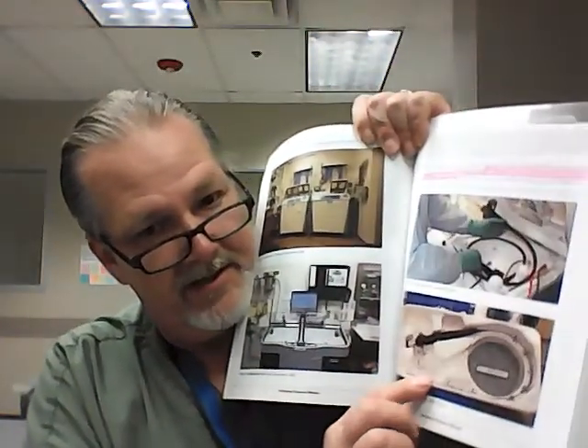This card right here is attached to a little chain, which is attached to a little cap. And the little cap is attached to the scope. This is extremely important: that cap must be attached to the scope before the scope is wrapped up and sterilized. The scope will get sterilized in a sterilizer that will draw vacuum. If you do not have that cap on, then you don't have the passageway open, there may be air inside of there, and that air will expand under the vacuum of the sterilizer and cause that scope to explode. Not like a Hollywood explosion, but it will definitely do some serious damage to the scope.